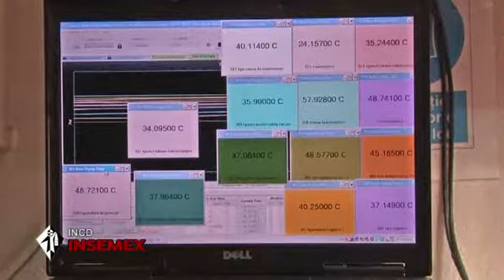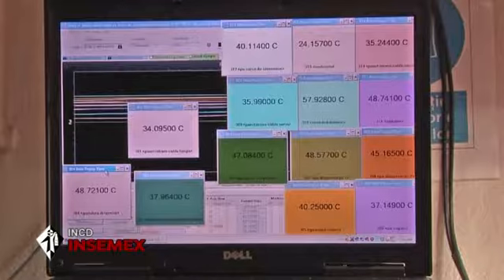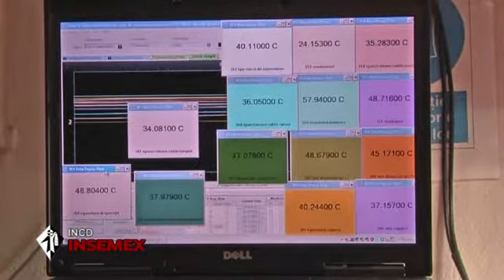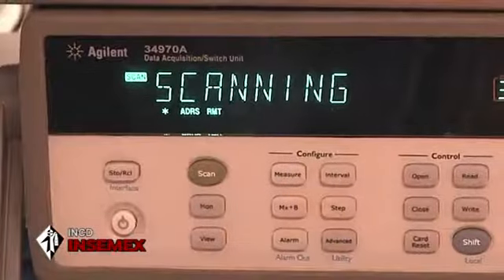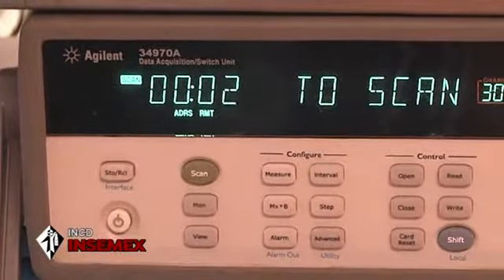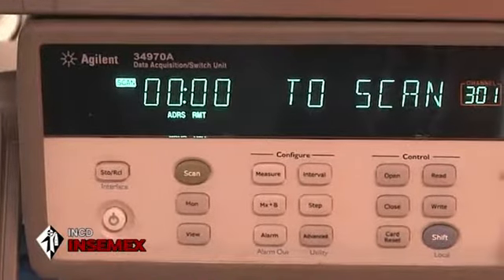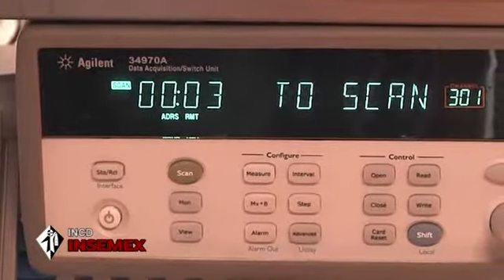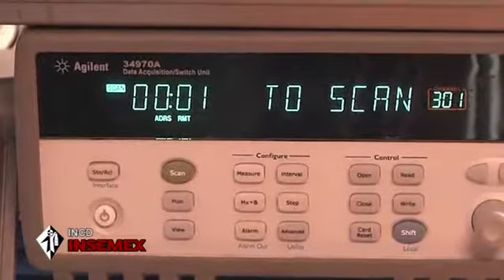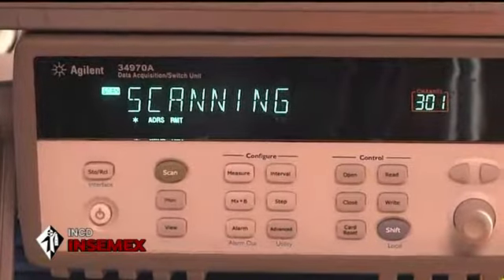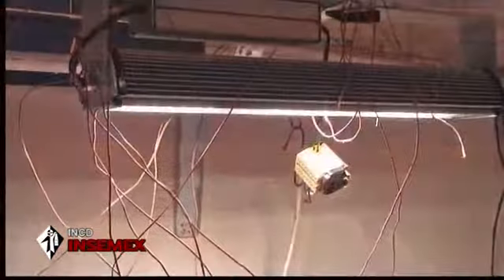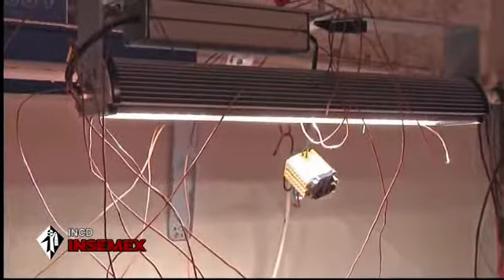The stand comprises an adjustable power supply, an Agilent multimeter with thermocouples and a computer for equipment commanding and acquisition of data resulted from the test. Depending on the equipment's type of protection, measuring the maximum surface temperature is performed on internal surfaces or on external surfaces of the equipment.